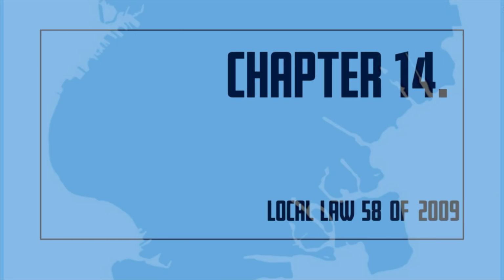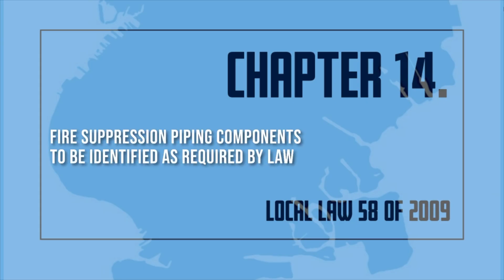Chapter 14. Local Law 58 of 2009. Fire suppression piping components as required by Local Law 58/2009. Note: only existing visible piping shall be identified as required. When ceilings are removed during renovations, any existing visible system piping shall be identified and painted.